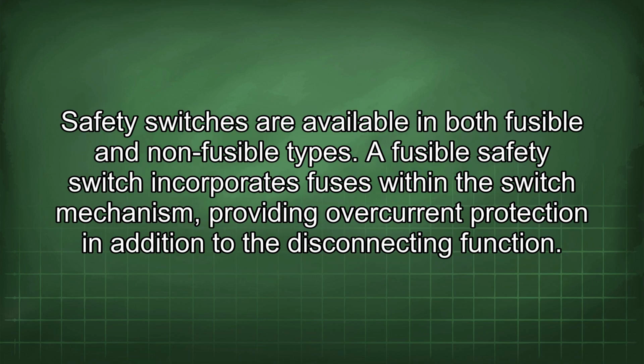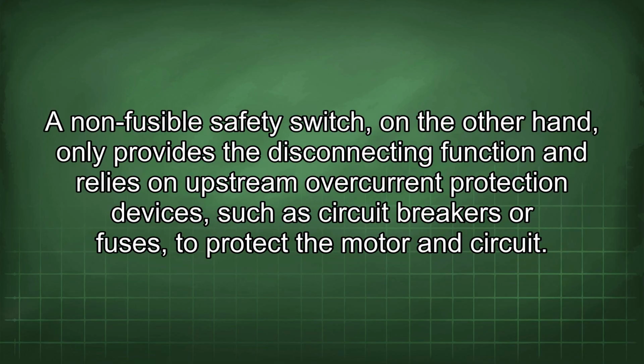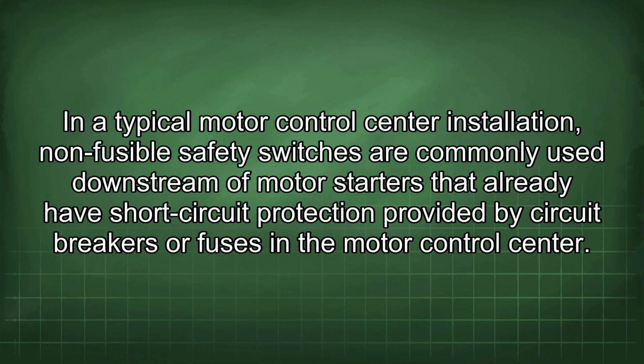Safety switches are available in both fusible and non-fusible types. A fusible safety switch incorporates fuses within the switch mechanism, providing overcurrent protection in addition to the disconnecting function. A non-fusible safety switch, on the other hand, only provides the disconnecting function and relies on upstream overcurrent protection devices, such as circuit breakers or fuses, to protect the motor and circuit. In a typical motor control center installation, non-fusible safety switches are commonly used downstream of motor starters that already have short circuit protection provided by circuit breakers or fuses in the motor control center.